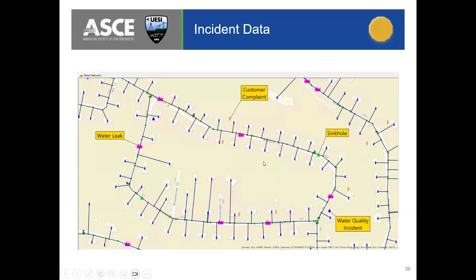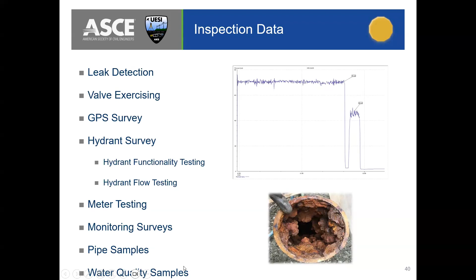And then more detailed hydrant flow testing, where we're seeing the effect of flow on the system. Meter testing, monitoring surveys, where we're recording the pressure at various locations. Pipe samples, like here, or coupons. So we can see the tuberculation, the thickness of the pipe, and water quality samples.